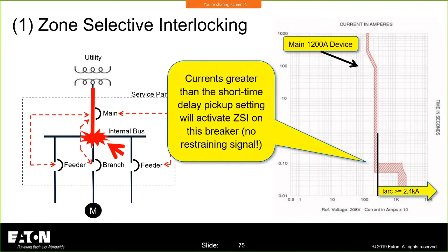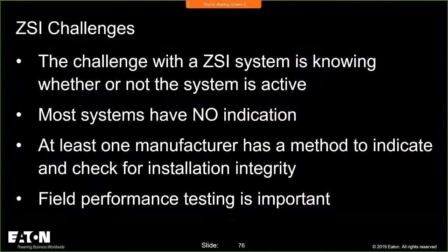And that's what it looks like on a TCC curve. There's your short time delay pickup. Your arcing current in this case has to be greater than 2.4, because usually if that's a 1200 amp device, the pickup of short time delay is around 2 times 1200, which is 2400 amps. And you always got to be on the plus side of that, because there's an error margin. There's a plus or minus associated with it.